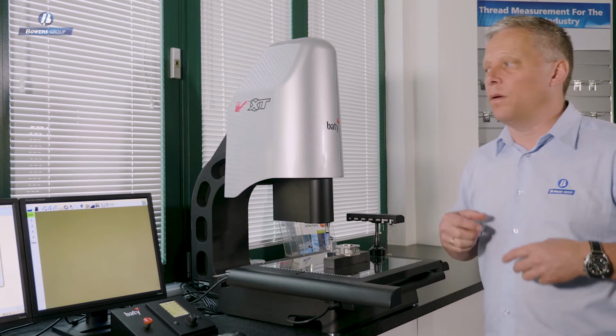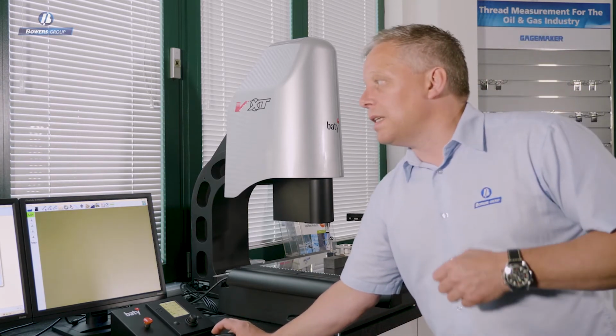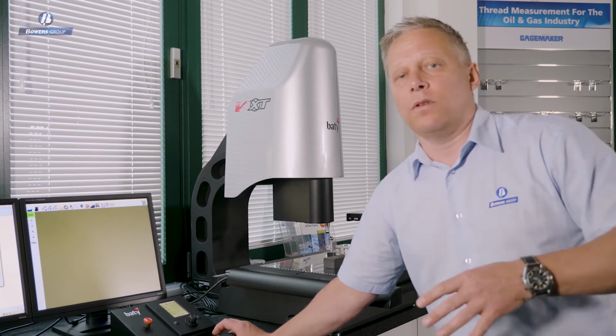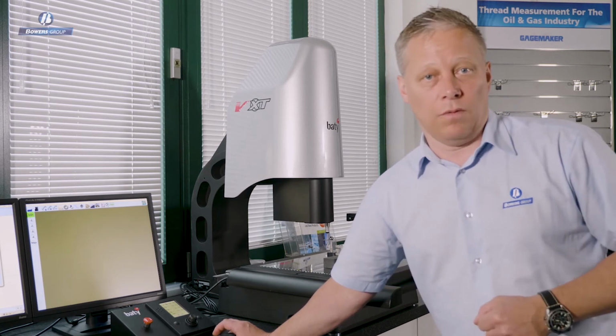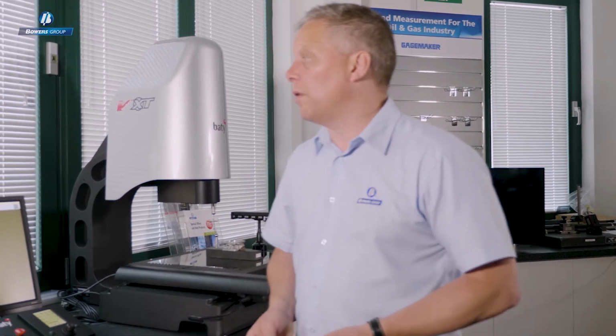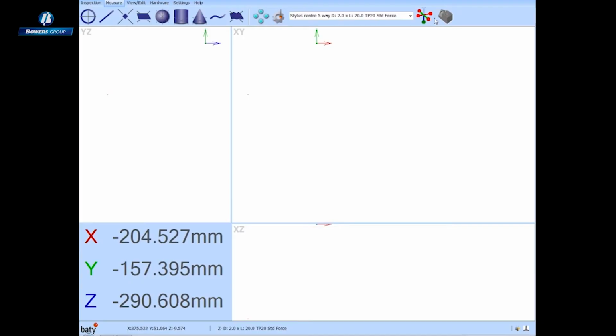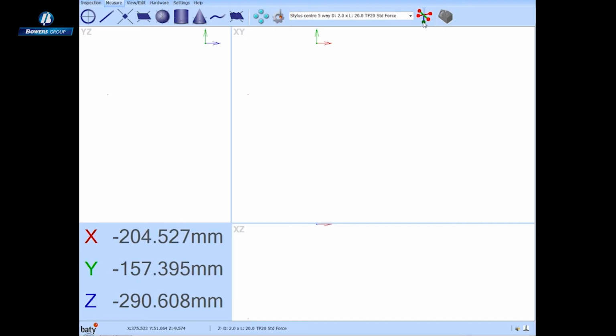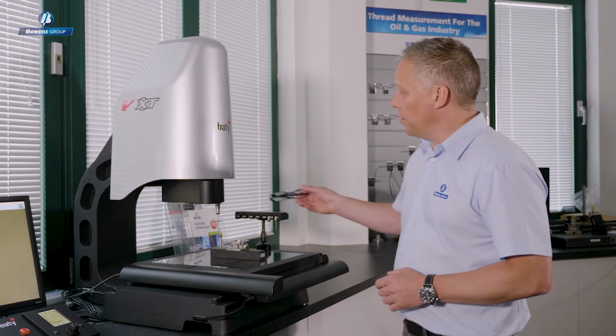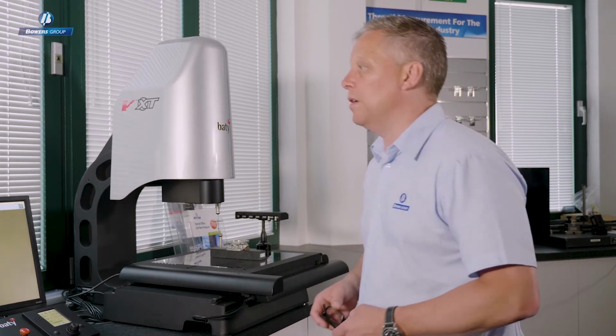tips and the camera. So having done this process now, I can select any of the tools in my probe library, and any dimensions that I make with any of those tools can all be related to each other because the offsets are known. So having calibrated all of the probe tips that I have assembled on this TP20 module, I can now use the little graphical icon that I've got here, which shows each of the tips that are assembled, and it's just a question of clicking on the tip that I want to use for the next measurement. I'm going to click on the Z down tip, that goes green, and now we can call for a plane measurement, and we're going to use touch probing to measure some of the features on this machined aluminium part.